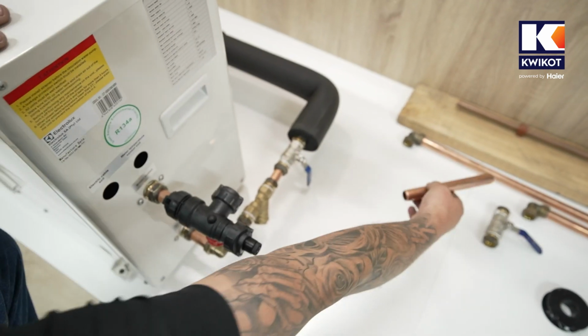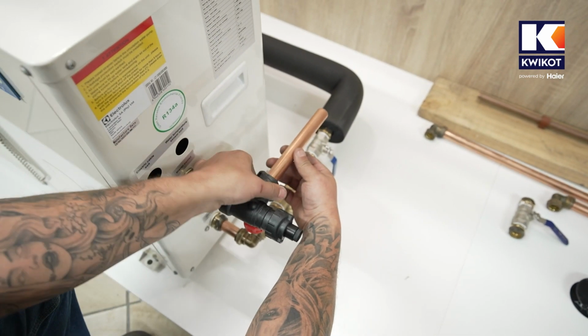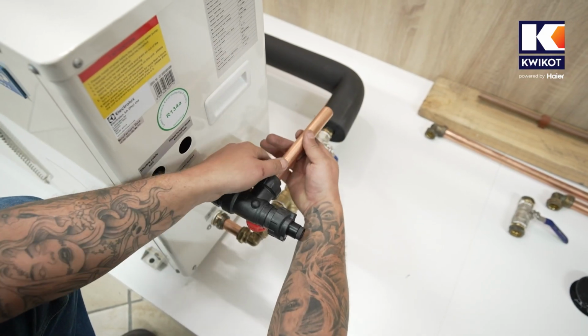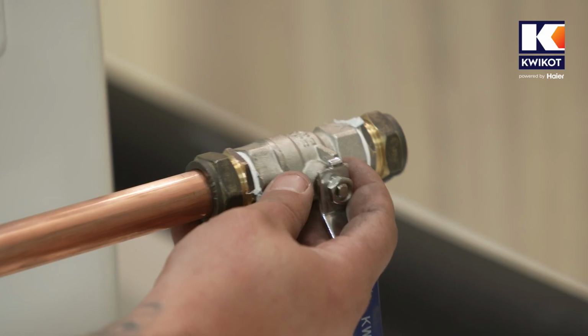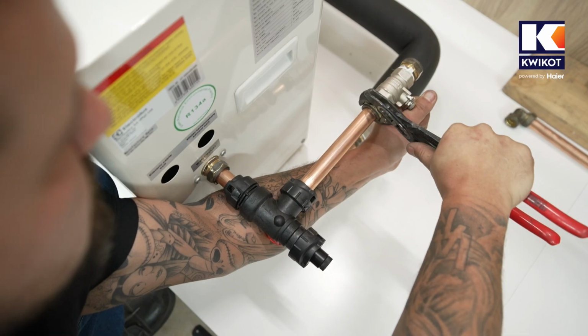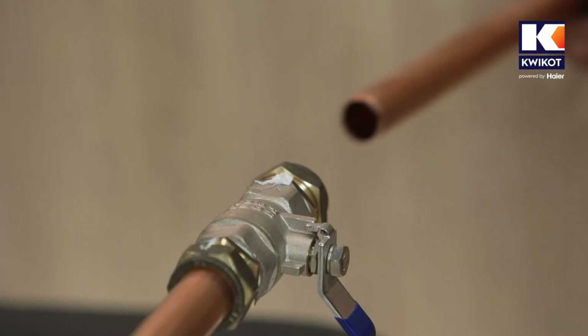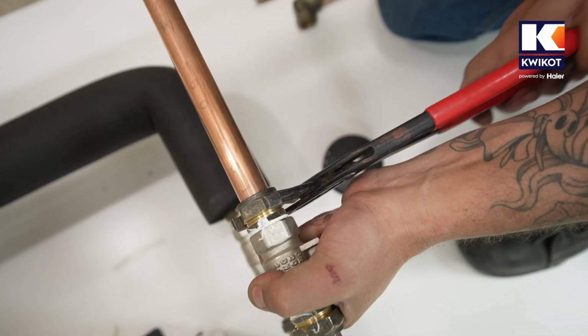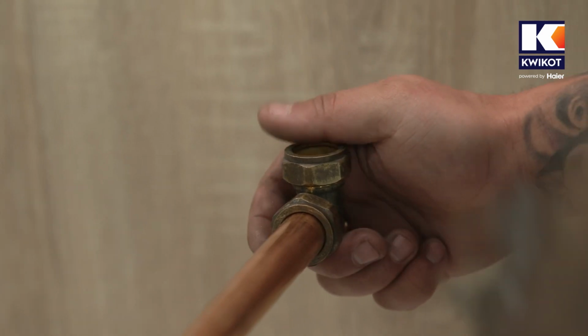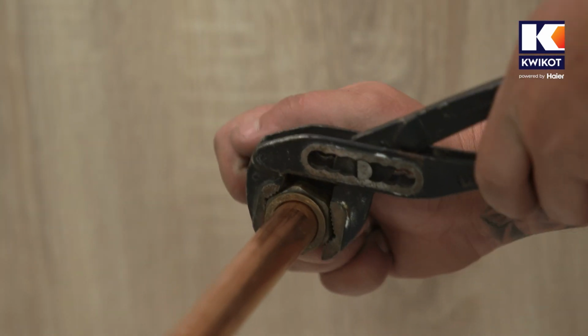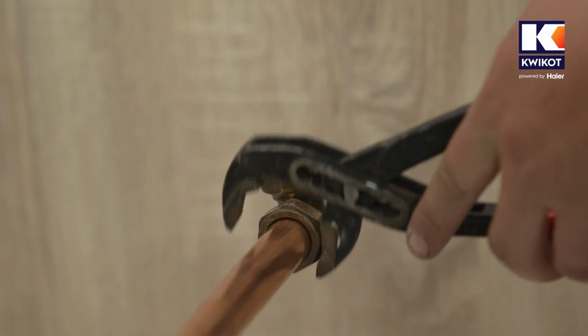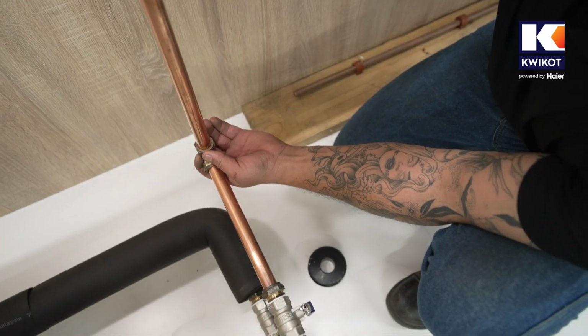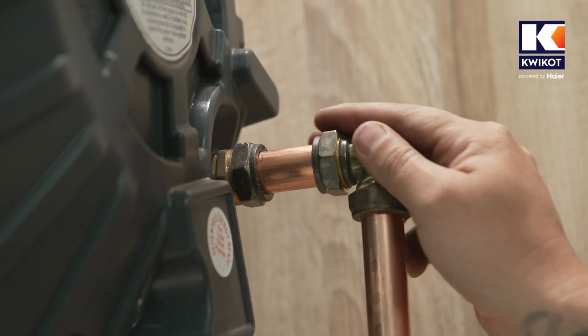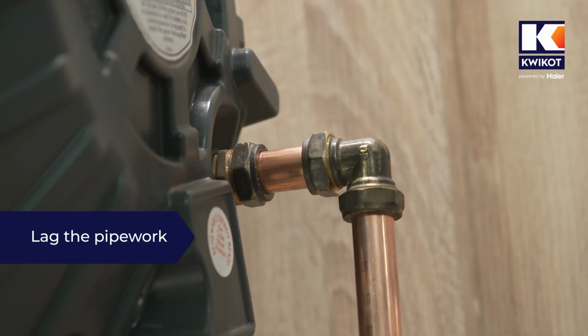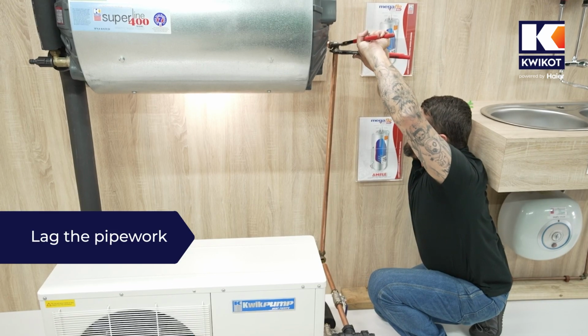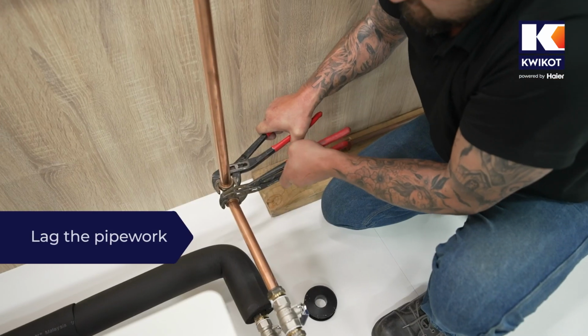And then we add this short length of pipe, to which we fit the second ball valve and tighten it. Next we add another length of pipe and tighten the ball valve, add an elbow and tighten it, and add a vertical pipe to connect to the water heater's renewable port and tighten it up. And then we tighten the elbow down below.